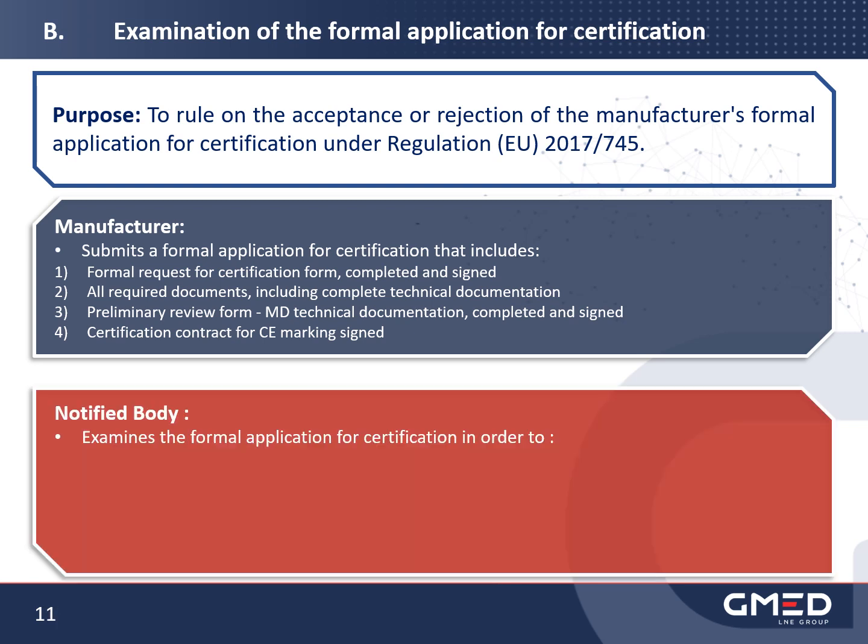The notified body must then examine the formal application for certification and, more specifically, the formal certification application file in order to ensure that the formal application for certification is complete, i.e. that all the documents requested and expected by GMED have been sent by the manufacturer and are included in the manufacturer's formal application for certification.